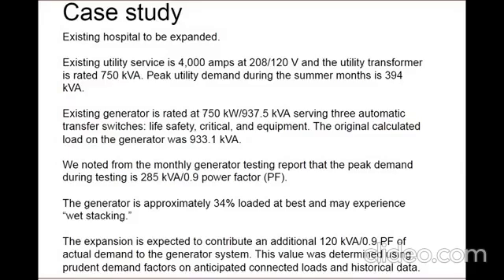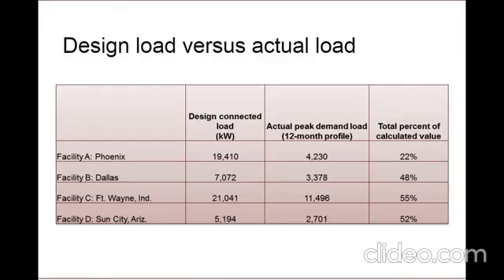We anticipate the expanded area to contribute an additional 120 kVA at 0.9 power factor. The expected demand on the generator after the expansion is about 400 kVA at 0.9 power factor. This is closer to 50% of the available capacity. So the generator is still much larger than it needed to be, but with the additional expected demand, the probability of wet stacking is reduced. Now, Dana will give an overview of design load versus actual load.